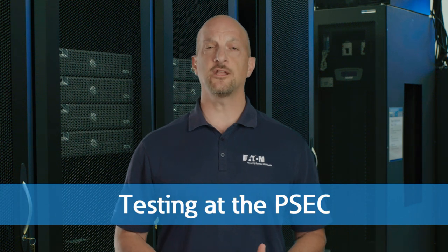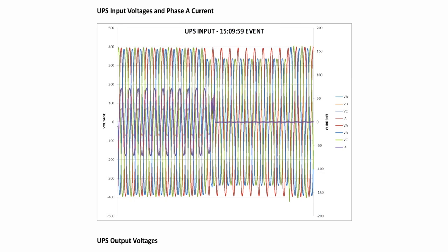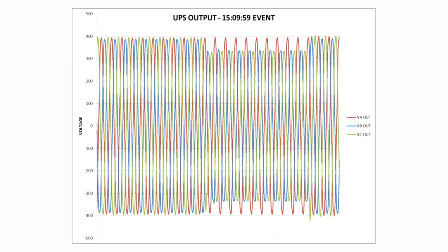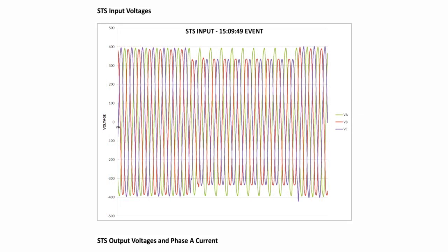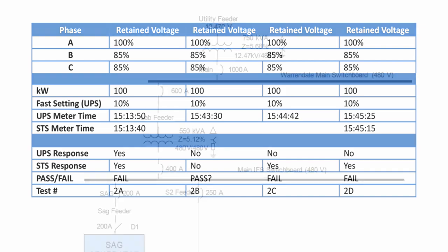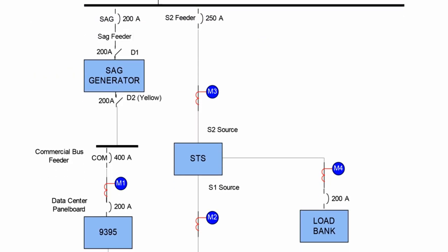One of our large financial data center customers had a problem with downstream static transfer switches interacting with our 9395 UPS systems. Our field service organization worked with the customer to determine the details of the problem, and we were able to reproduce the issue here at the PSEC. By simulating the field condition, we were able to test and offer a solution that involved adjusting settings on the static switch and on our UPS system. The partnership with our field service organization works very well, benefiting not only Eaton, but our customers.